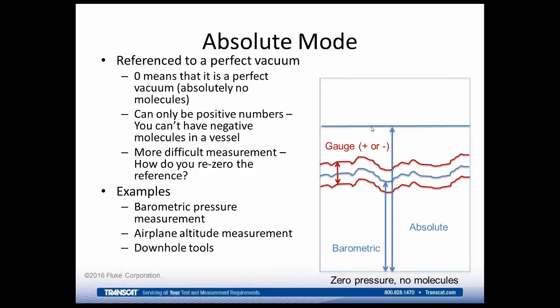It's not an impossible situation, but it does make it slightly more difficult than your normal gauge mode calibration. Some examples of absolute mode are the barometric pressure measurement. So as we said, the pressure in the room, by definition in gauge mode, is 0. So that's not very useful to us.